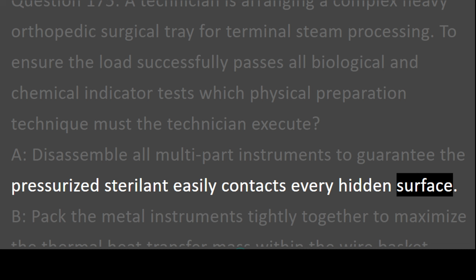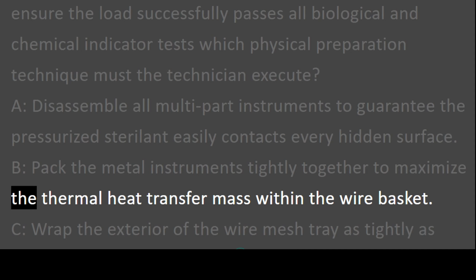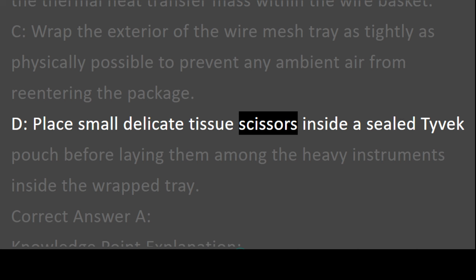A. Disassemble all multi-part instruments to guarantee the pressurized sterilant easily contacts every hidden surface. B. Pack the metal instruments tightly together to maximize the thermal heat transfer mass within the wire basket. C. Wrap the exterior of the wire mesh tray as tightly as physically possible to prevent any ambient air from re-entering the package. D. Place small delicate tissue scissors inside a sealed Tyvek pouch before laying them among the heavy instruments inside the wrapped tray.